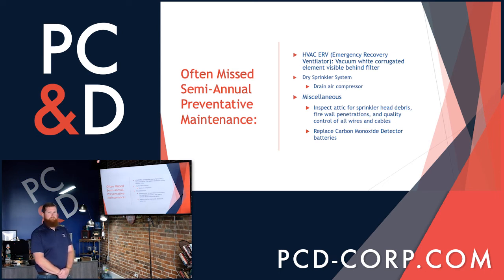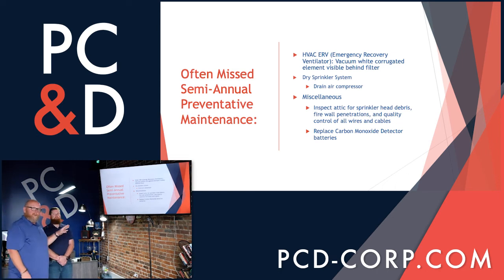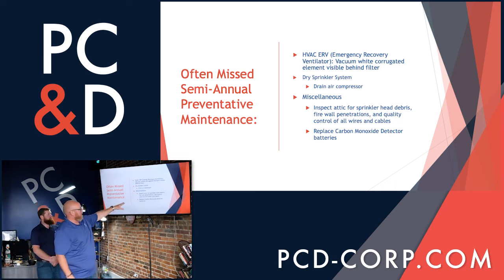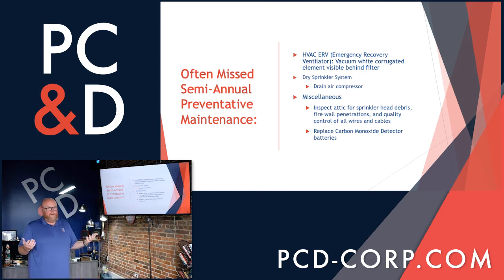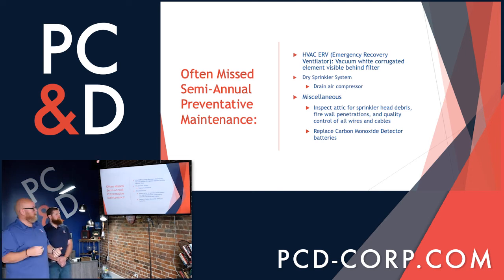So one other thing I want to touch on briefly, when Travis mentioned the sprinkler heads in the attic and free of debris, you may think to yourself, I was in the attic 4 years ago, everything looked fine, what's changed? There can be a lot of change, and a lot can change quickly. So a couple of examples of how the situation in the attic can change, and it might change even overnight. Especially if you have a shingled roof or a pitched roof and you truly have an attic space.